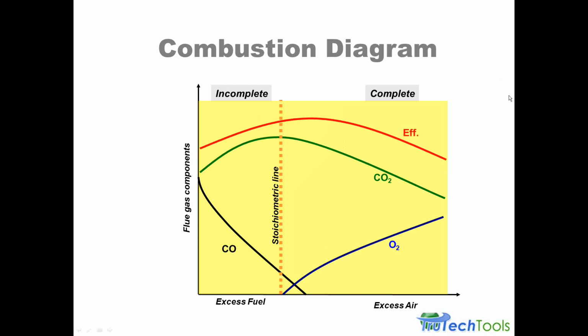Here's a line where we plotted, the red line, the combustion efficiency. So this is to give you an idea of where the efficiency peaks out and where you'd see the manufacturer's combustion equation. So a peak, or the highest amount of efficiency available for the type of fuel and the equipment that you're running on. And I'll throw in a line now for smoke, and that would be the carbon particles. That's the purple line we just laid in down here. And again, it comes from very high levels when there's just not enough oxygen available and you're getting raw carbon moving through the system and forming carbon soot particles. But again, in the real world, that soot number or smoke number can come down and down and down when you have enough oxygen available to fully combust the fuel as you move through the stoichiometric area.